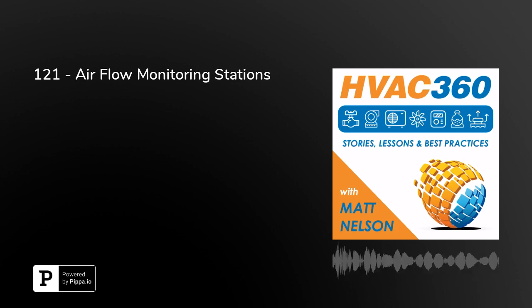So VAV boxes have these airflow measuring stations in the throat of the neck of the VAV box. I've seen some on air handling units where they actually come with the velocity pressure measurement probes already installed. But generally speaking, when I'm talking here, these are going to be kind of third-party devices that you're going to have to put into ductwork, whether on a new project, or you can even retrofit these into existing ductwork. So most of the airflow monitoring stations that I'm going to be talking about are separate.